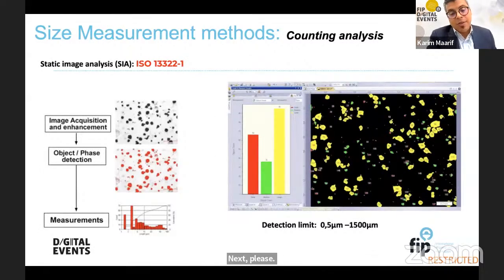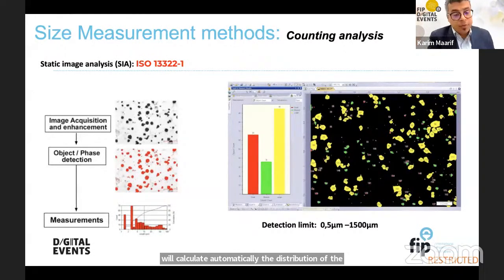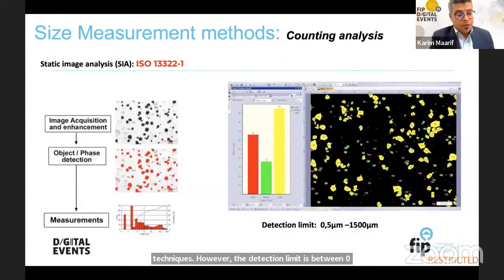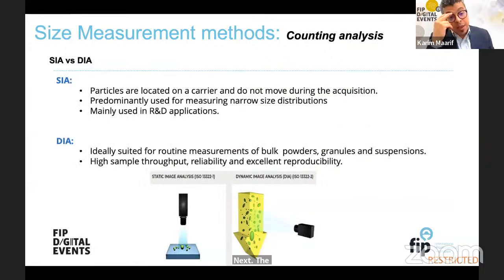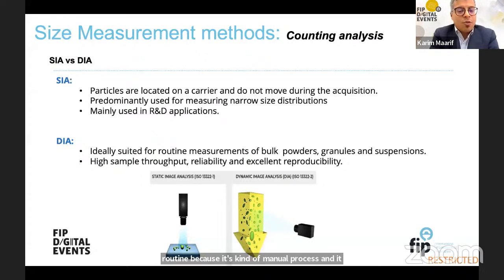For static image analysis, the sample is put on a sample holder and we have two phases: image acquisition and image detection. The computer automatically calculates the distribution and size of particles, and we can also get information about particle shape. The detection limit is between 0.5 to 1,500 micrometers. The difference between static image analysis (SIA) and dynamic image analysis (DIA) is that SIA is mainly used in R&D applications, not routine, as it is a more manual process and concerns narrow distributions.